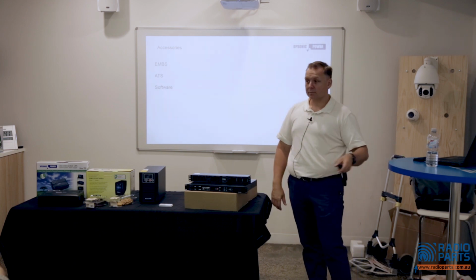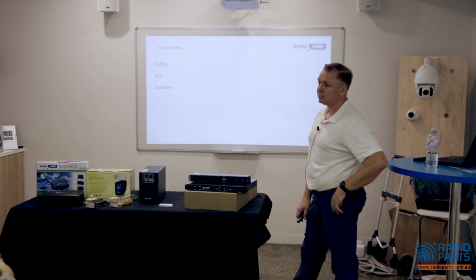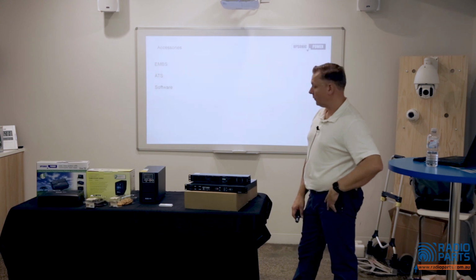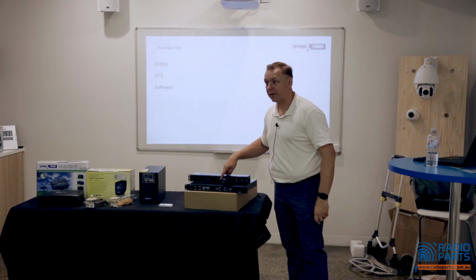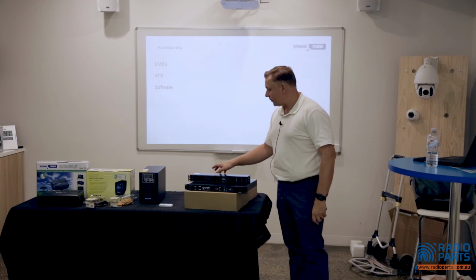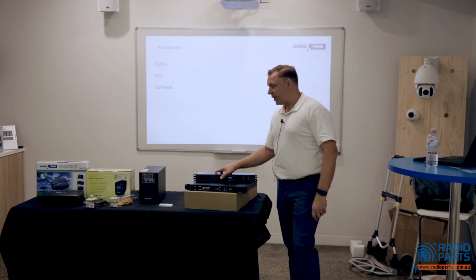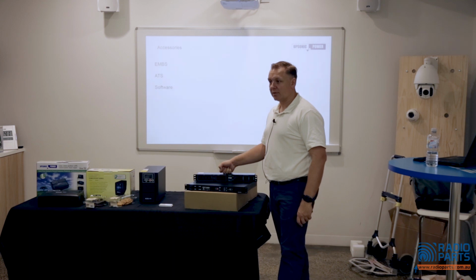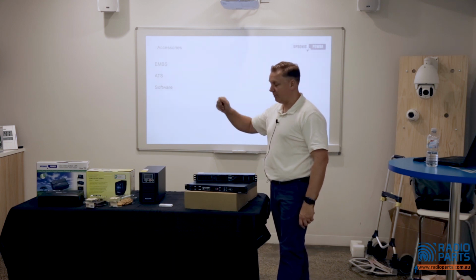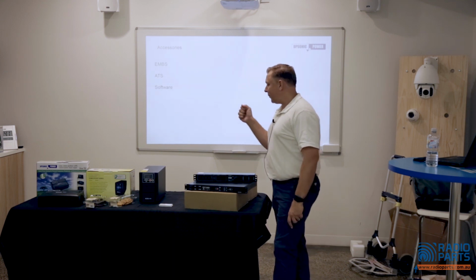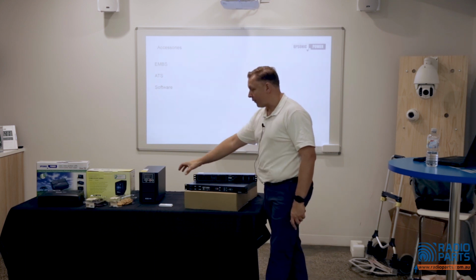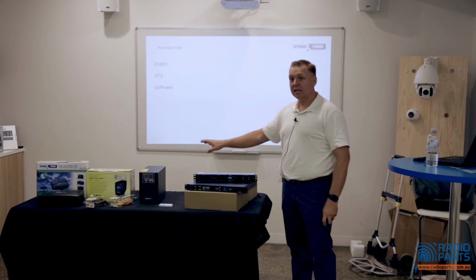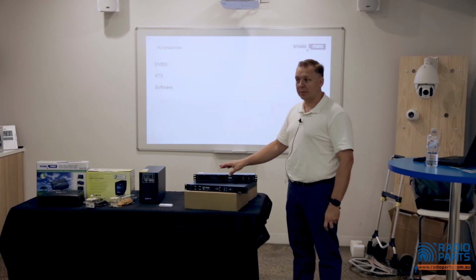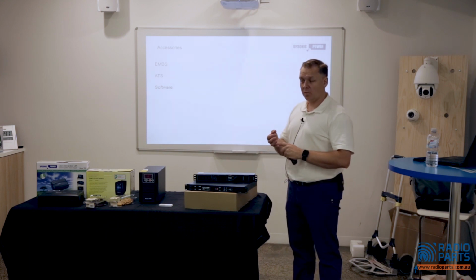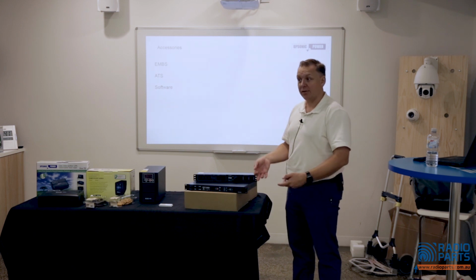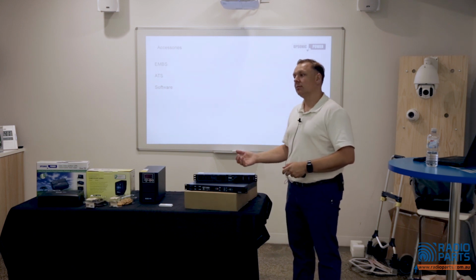I've seen the large box one. Yep. Before this rack one, though, does that need to be hardwired? No, it's just all IEC plugs on the front. So yeah, exactly. With this, you typically put that into the back of the rack, because odd-looking things inside the rack, people play with them, which is bad. But yeah, it allows you to have a small pluggable style UPS, but you're still able to do that maintenance or replace it if there's a failure or a problem as well without turning off the supply.